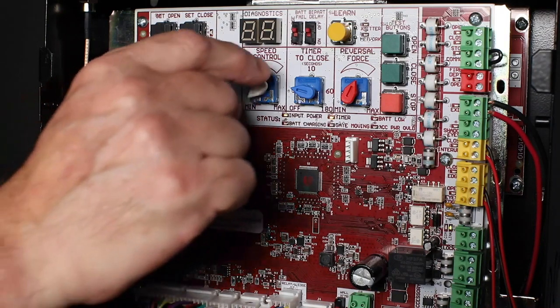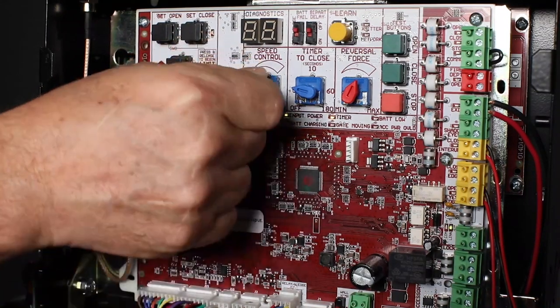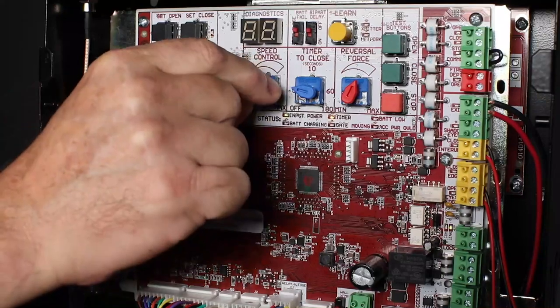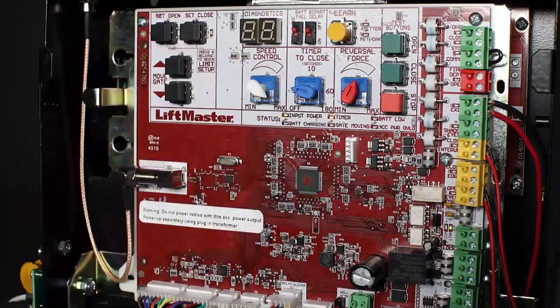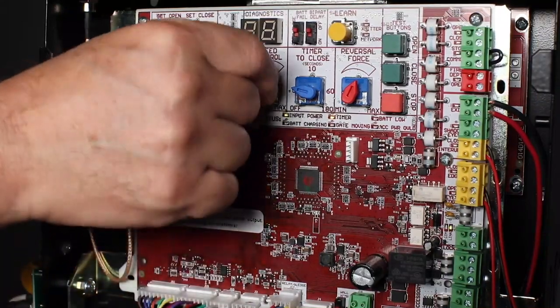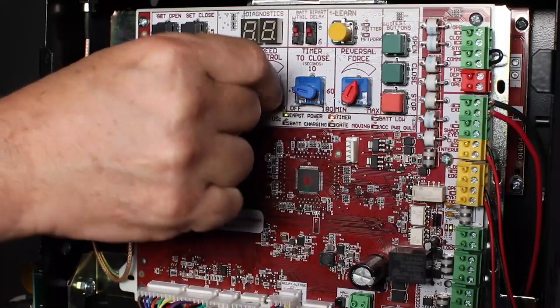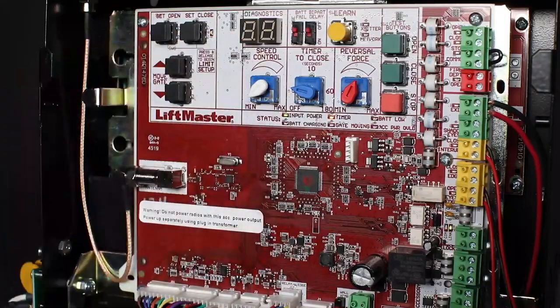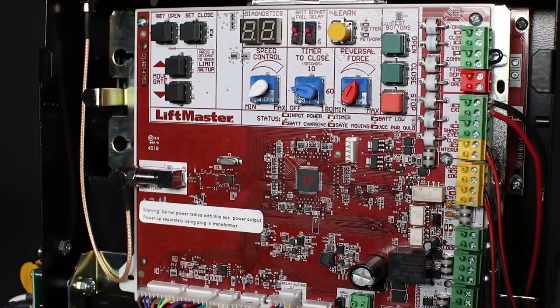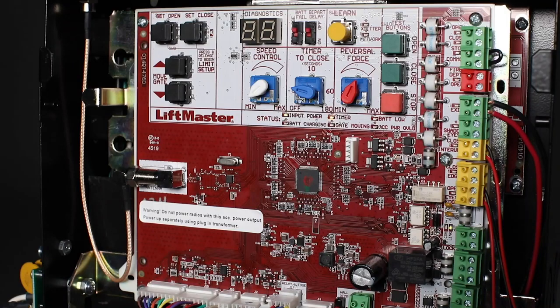The HDSL24UL can be adjusted to speeds ranging from a half foot per second to one foot per second. And the HDSW24UL can be adjusted from 13 to 36 seconds for a 90 degree opening. The default setting is to the lowest speed.